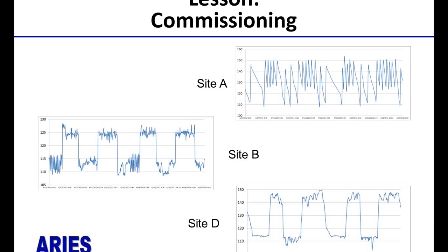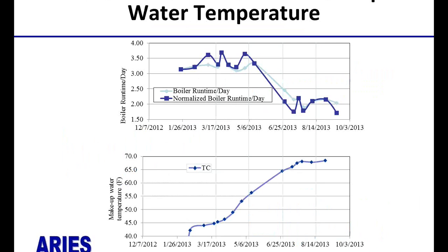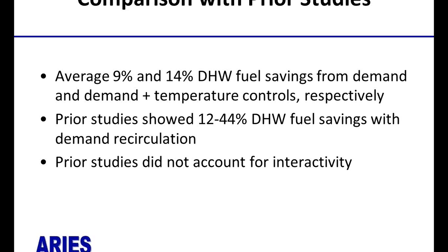For Site B, this is the building that had the mixing valve and not a storage tank, and it looks like it did a pretty good job of maintaining the desired temperature set points. At Site D, again with a storage tank, the lower bound temperature seems to have been met, but the upper is skewed well above 125 degrees, and this diminished savings. This graph reiterates and illustrates that correlation between boiler runtime and makeup water temperature as it varies over summer and winter. And you can see a strong inverse relationship here.